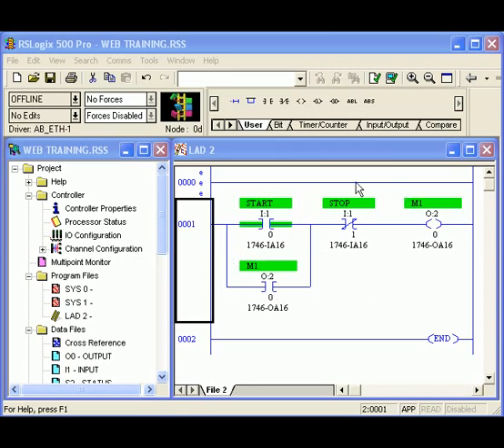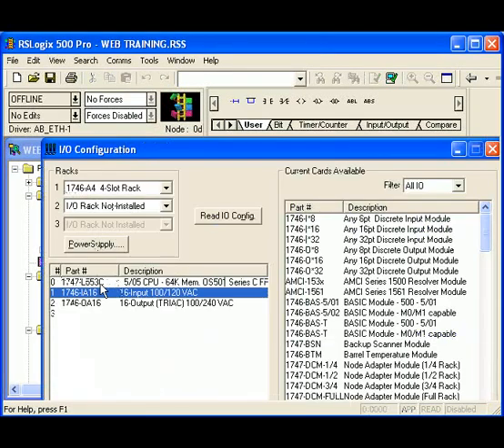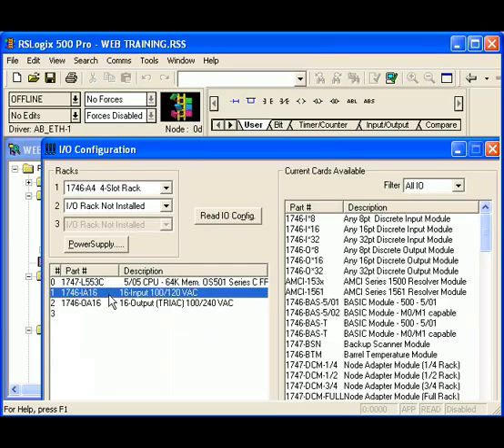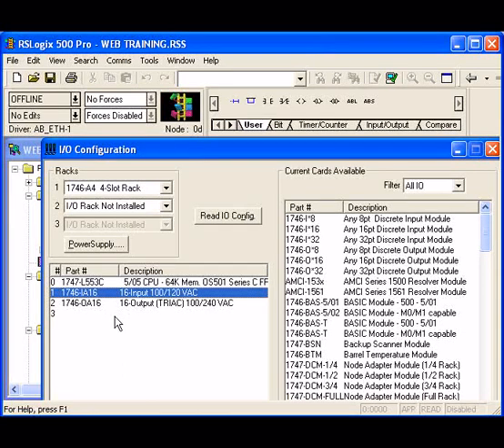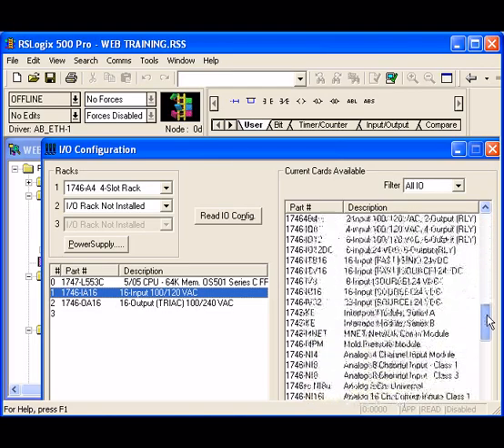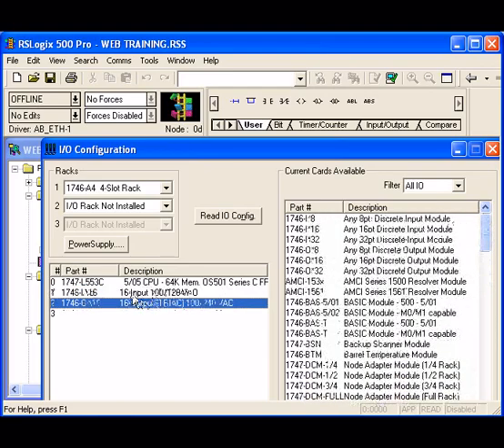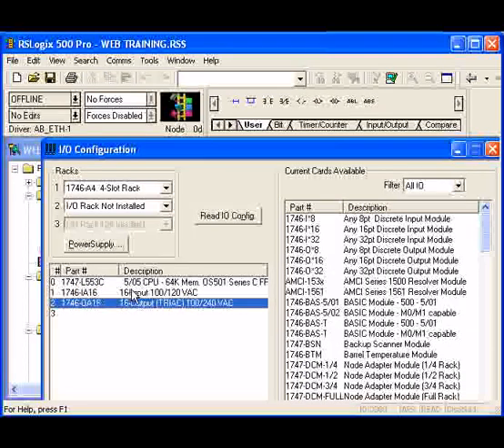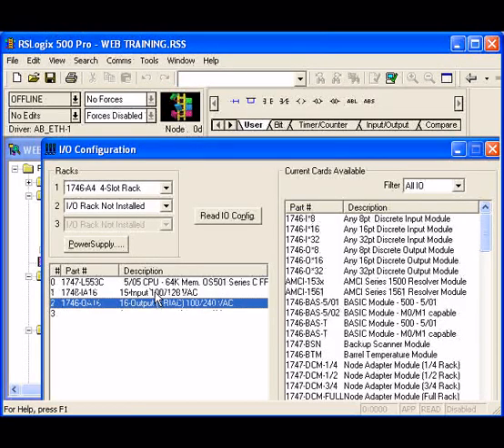We have right now the same kind of ladder designation that we showed on one of our earlier slides. And we want to look over here and look at the IO configuration of the processor. We notice we have the processor here and if you remember, a PLC is generally a rack mounted type device. In other words, you have slots. We have a slot where the PLC would be. You have a slot where input and output cards would be. And each of them have their own little location in that rack. Now, we have over here a whole bunch of different IO cards that are available that we can use for this particular PLC. I have chosen an input card and an output card. They're both 16 inputs and 16 outputs. They both have 16 channels, shall we say. And they both will work with a 120 volt signal. This is perfect for dealing with motors and contactors that use 120 volt coils and in an area where we need to use 120 volt signal levels.